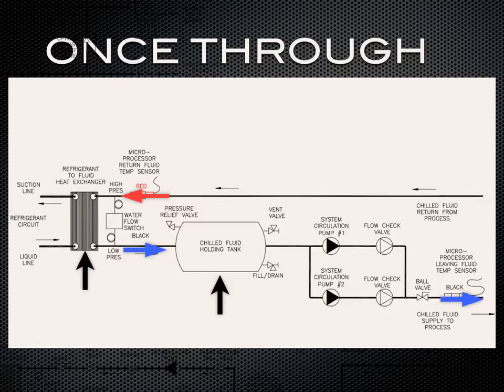You're going to notice that there's 2 system pumps on this setup, and sometimes that's just an option to have a backup pump. But one thing to keep in mind about the once-throughs is that there's one loop, and that one loop is directly tied with that chiller evaporator. And once I get into the pros and cons, I'll get into a little more depth of how that one loop is really tied together with your process and your chiller evaporator.